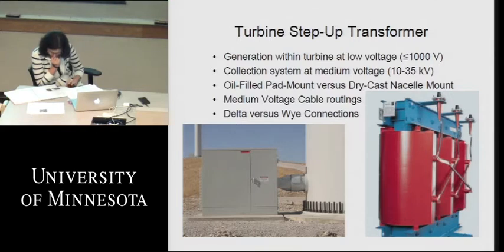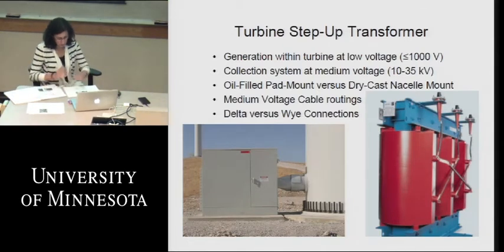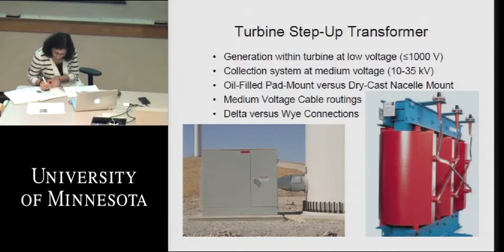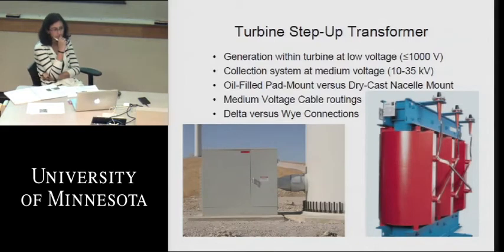So the generator, like I said, usually operates at 1,000 volts or below. This is done so that we can use conventional electricians, not electricians who are medium voltage licensed, which is a special license and takes a high degree of training to get. The pool of electricians isn't that large at medium voltage, given the scale at which wind builds all these plants at the same time. So if we keep the generator and all the components in the nacelle below 1,000 volts, we can use conventional licensed electricians as our wiremen for the installation and commissioning of this equipment.